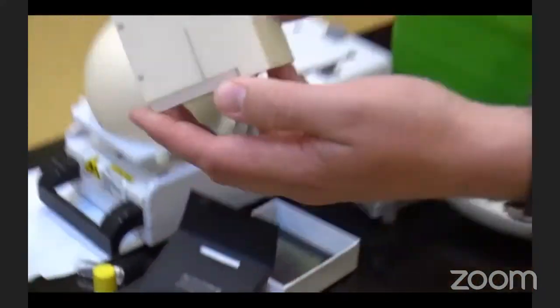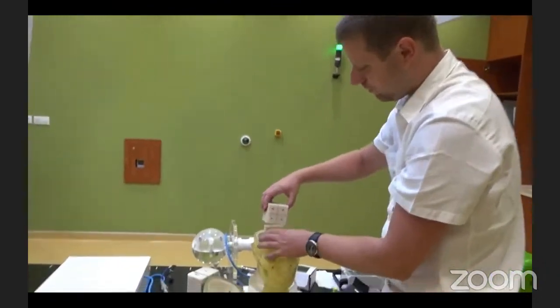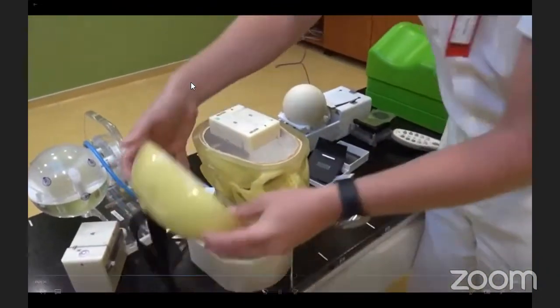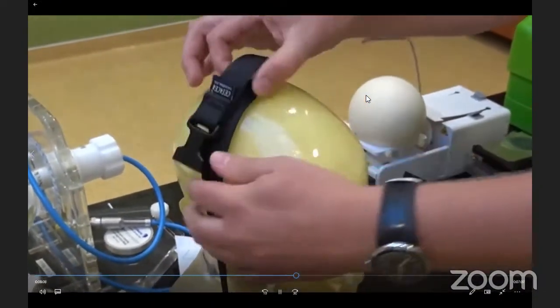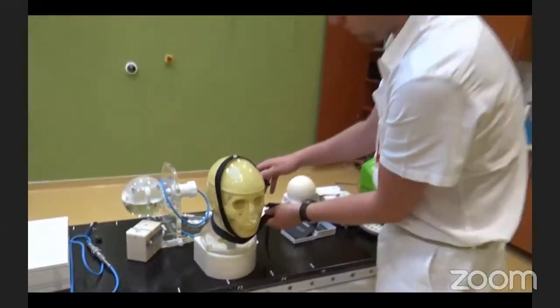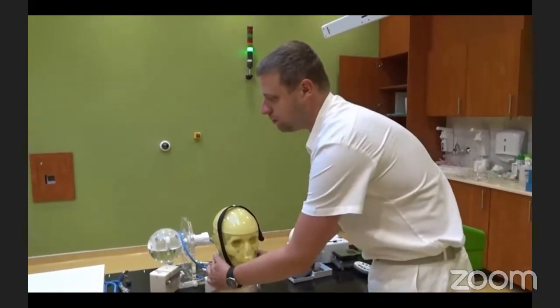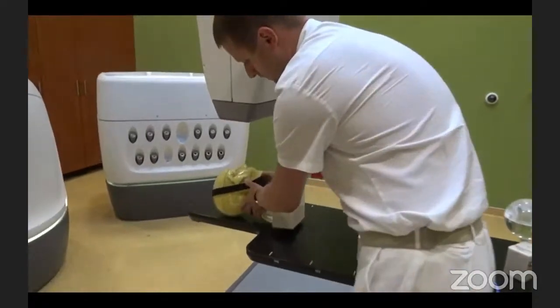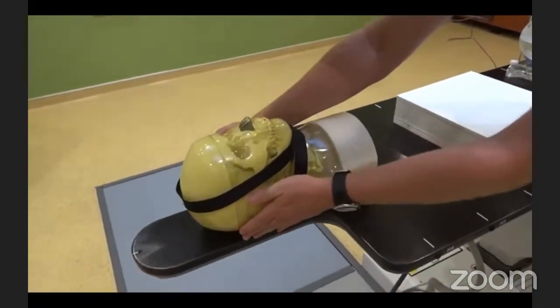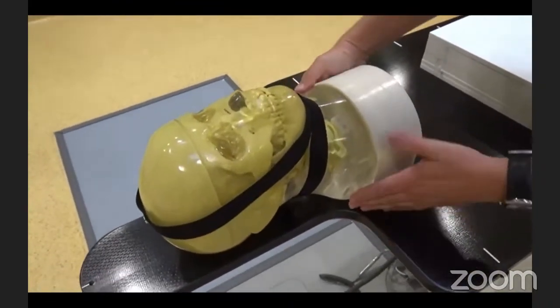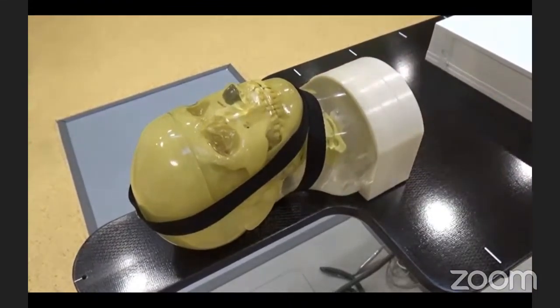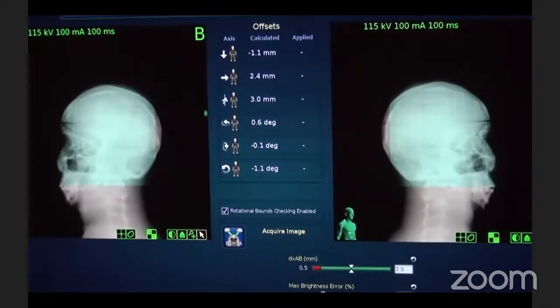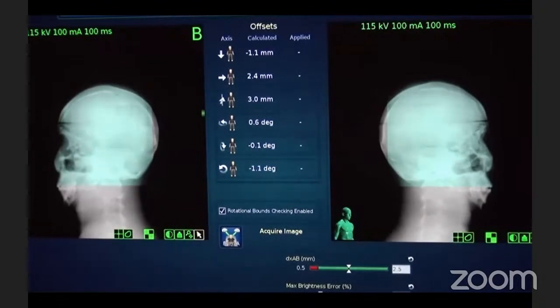And then we position this ball cube in the middle of the head. And we position the head phantom on the couch. And we'll deliver a simulated treatment on the phantom. For the end-to-end test and also for Lucy phantom and synchrony phantom measurements, first we check the phantom position on the couch. If any correction is needed, we correct it by the couch, and verify the new position.